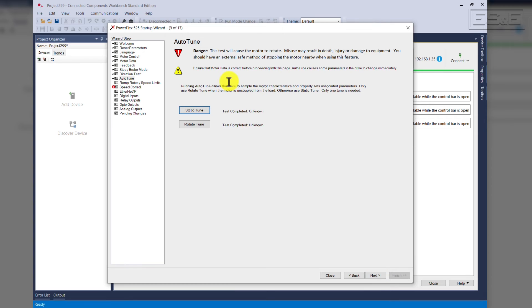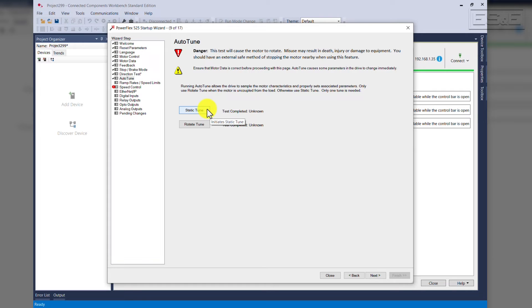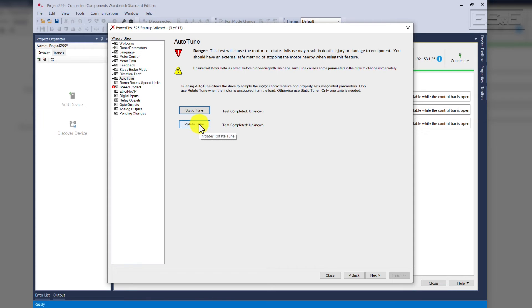This brings us to the Auto-Tune. You have two options, Static Tune and Rotate Tune. If you're coupled to a conveyor or pump, you want to use a Static Tune. That means the motor will do the tune, but will not rotate. A Rotate Tune gives you a more thorough tune, but you must be uncoupled from your load. For this application, we will do a Rotate Tune. Just press Rotate Tune.